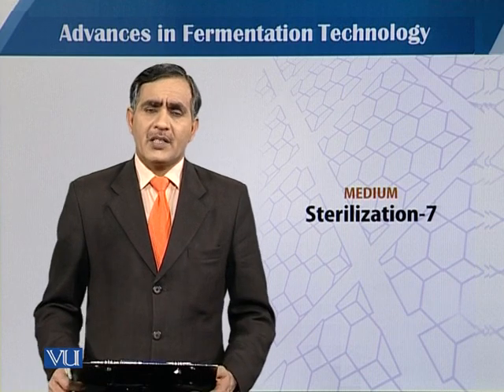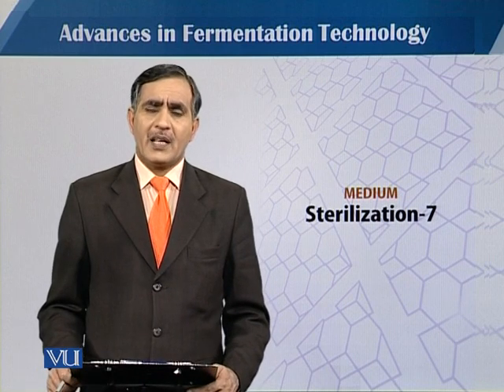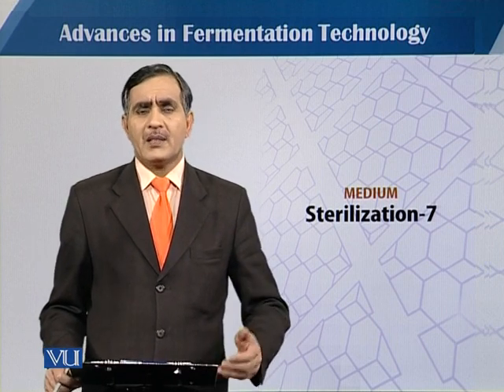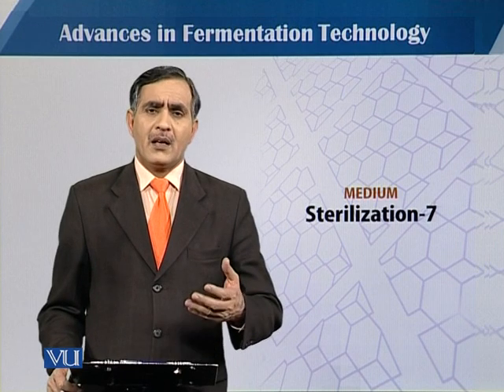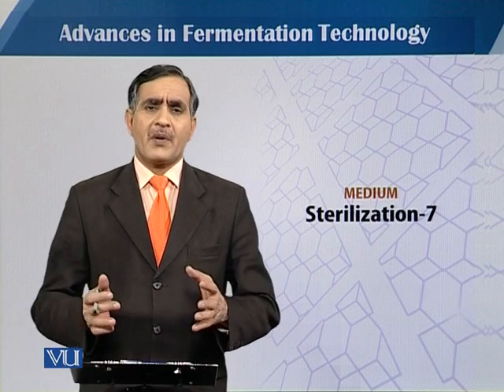Concerning the sterilization process, we can classify sterilization into various types. One is in-situ sterilization and the other is ex-situ sterilization. In-situ sterilization means sterilizing the fermenter in the same place where it is — we supply steam directly to the fermenter. Ex-situ sterilization is only applicable at small scale or shake flask level, where we place the vessel into an autoclave to sterilize.